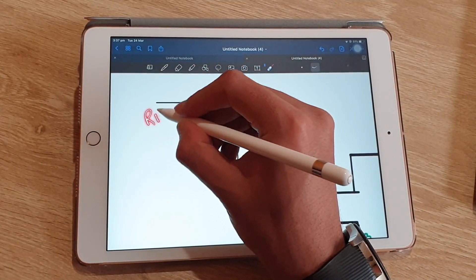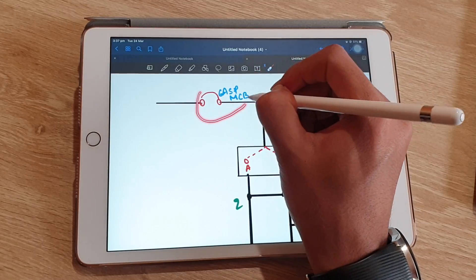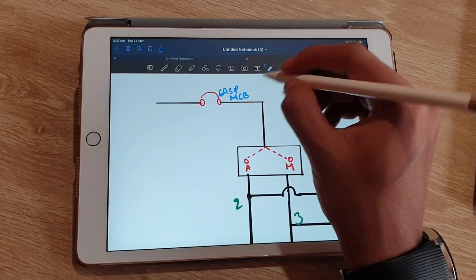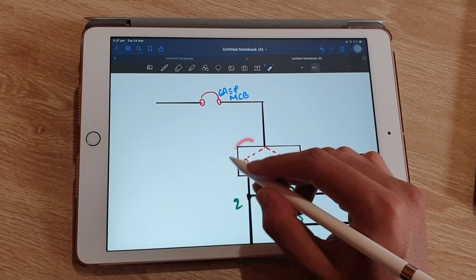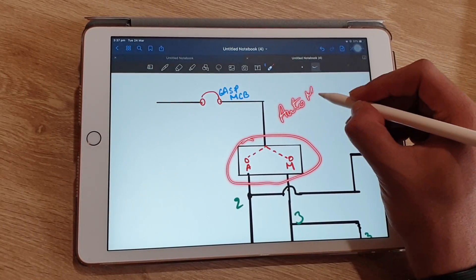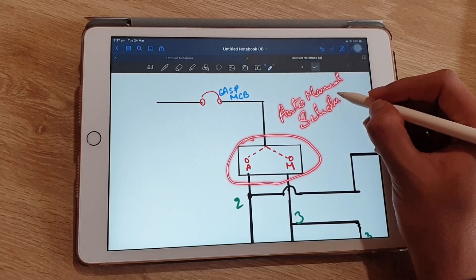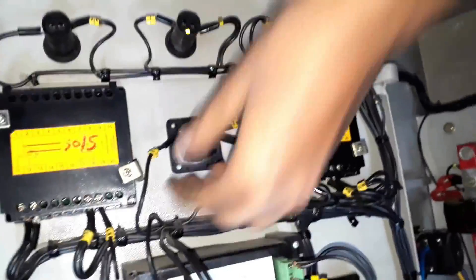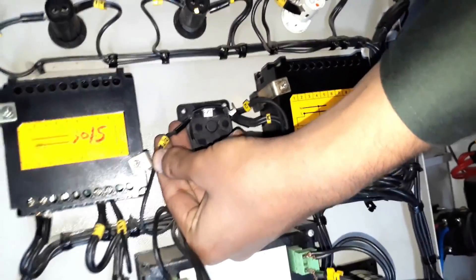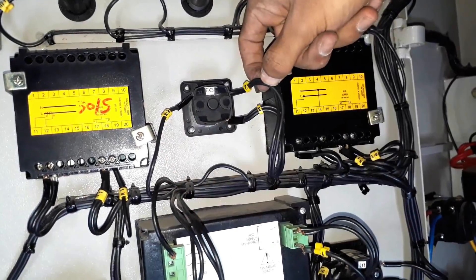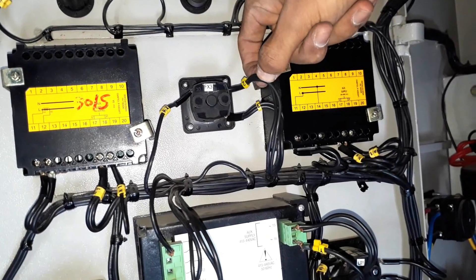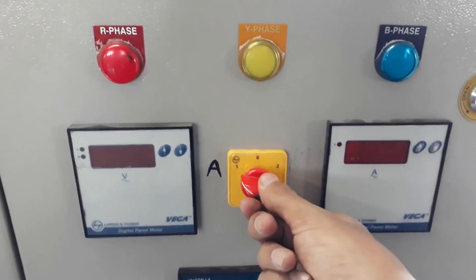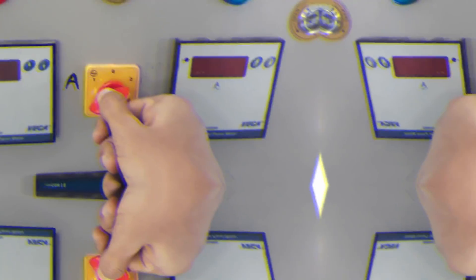To the R phase I am connecting a 6-ampere single-pole MCB in this panel. From this circuit breaker I am connecting this phase to an auto-manual selector switch, which is used for switching between auto and manual mode. From the MCB I am taking a wire out labelled R2 and connecting it to the auto-manual selector switch. From this switch there are two output ports: number two is used for auto and three is used for manual mode, and from each terminal two wires are taken out.